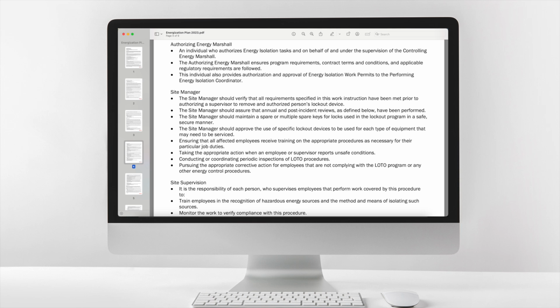The site manager should assure that annual and post-incident reviews, as defined below, have been performed. The site manager should maintain a spare or multiple spare keys for locks used in the lockout program in a safe, secure manner. The site manager should approve the use of specific lockout devices to be used for each type of equipment that may need to be serviced. Ensuring that all affected employees receive training on the appropriate procedures as necessary for their particular job duties. Taking the appropriate action when an employee or supervisor reports unsafe conditions. Conducting or coordinating periodic inspections of LOTO procedures. Pursuing the appropriate corrective action for employees that are not complying with the LOTO program or any other energy control procedures.